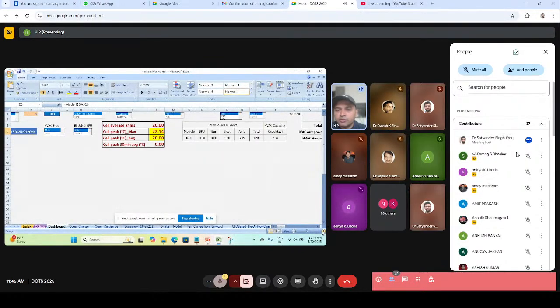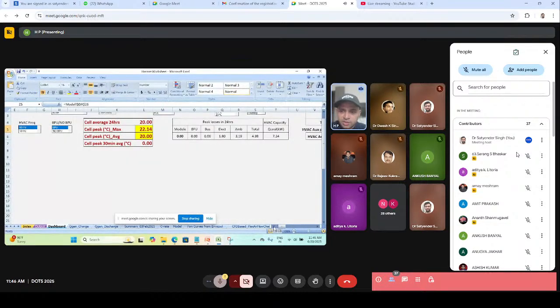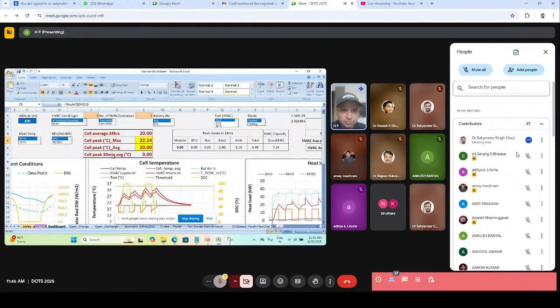This is a working Excel sheet which I generally use to design the battery energy storage thermals. I look at variables, starting with altitude. As we go higher, the density of the air reduces, and thereby the effectiveness of thermal systems reduces, because the air doesn't have as many cool particles in the same volume, so we need more air. Or if the same system is used, it will be less effective in terms of cooling.